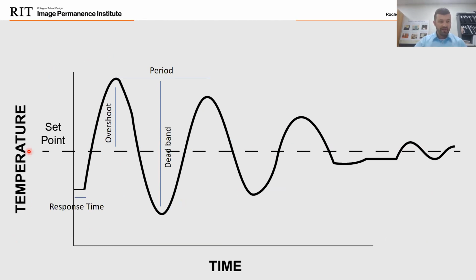So here we have the set point for the unit, this dotted line that's running here. We'll say this is 70 degrees. We're aiming for 70. There's our 70. So the response time: we make a change in set point. We adjusted the set point. We were at 68, so here's the response. The unit is now conditioning to 70. We go, but we pass it by.